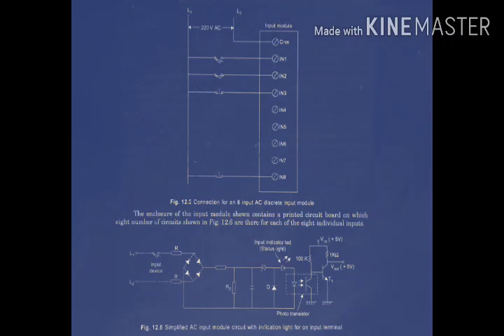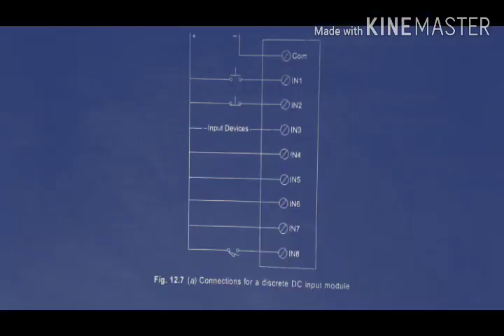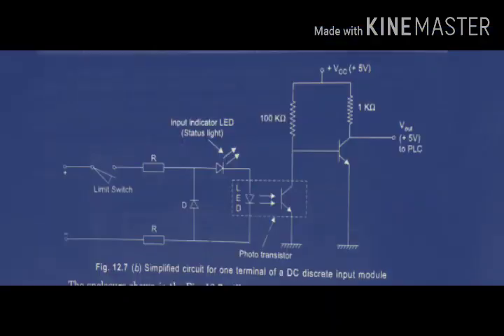So this is the role of the input module. This was AC input and there is also DC input. For AC input module, figure 12.6 applies. When you use DC input, you don't need a rectifier — in figure 12.7, this is DC input with positive and negative, so the rectifier circuit is not needed. The enclosure shown in 12.7 will contain 8 such circuits, giving 8 DC inputs.